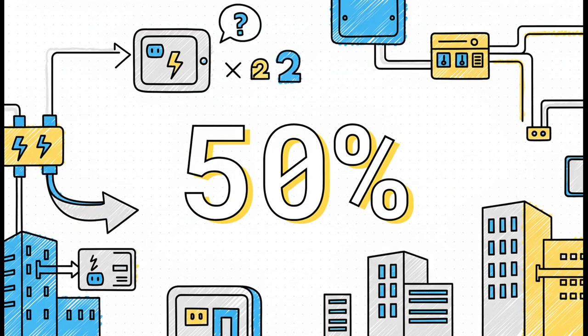But here is the really clever part. For everything above that initial 10,000 VA, the code lets you apply a demand factor of just 50%. It's basically a calculated bet, based on mountains of data, that you're probably only going to use about half of the remaining available power at any given moment.